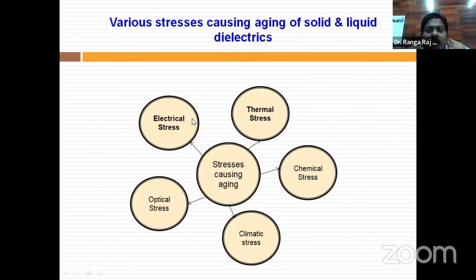These two stresses degrade the performance of the insulation as well as the overall performance of the electrical machine, whether transformer, motor, or generator, rotating machines, DC or AC. In every machine we find these insulating materials. The minor stresses are chemical, climatic, and optical stresses, but their effect on machine performance is much less. So the major two stresses are thermal stress and electrical stress.